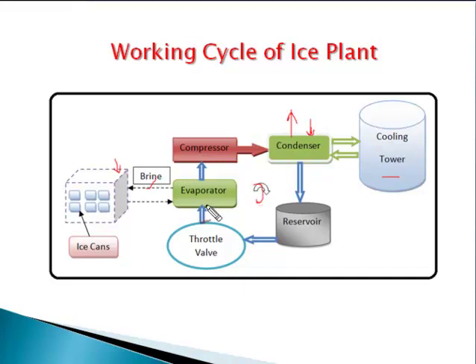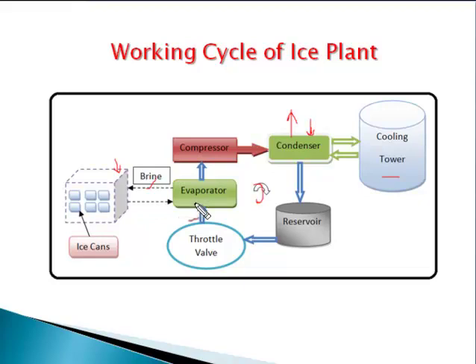Now we will look at the secondary cycle, which is completed by the brine solution. This is also known as the secondary refrigerant. The brine solution enters the chilling tank from the ice cans, absorbs heat, and then that hot brine solution enters into the evaporator. There, the primary refrigerant absorbs the heat from the brine solution, making it cold. The cold brine solution then enters back into the chilling tank. This secondary cycle uses the brine solution as the working or cooling medium.